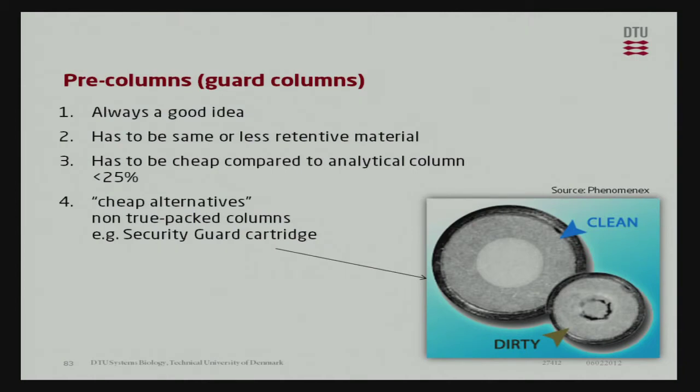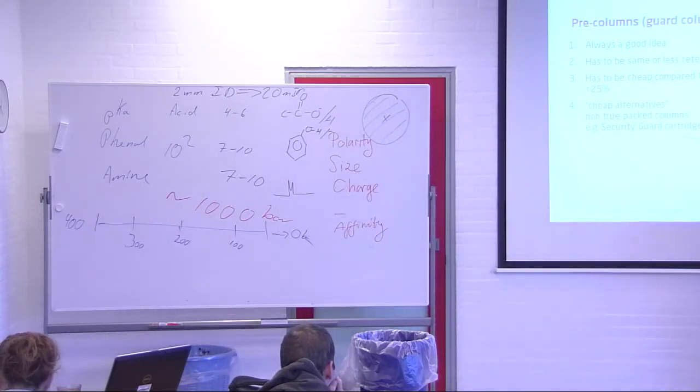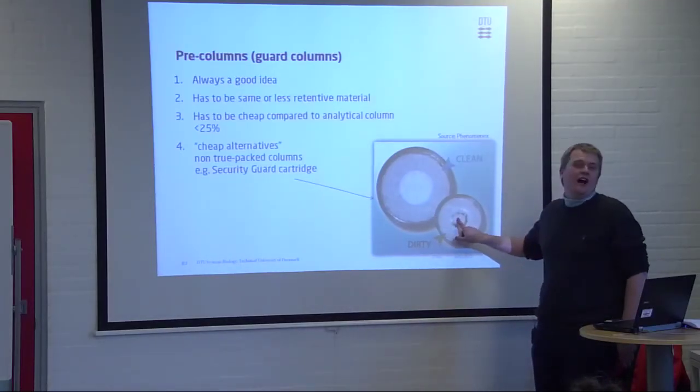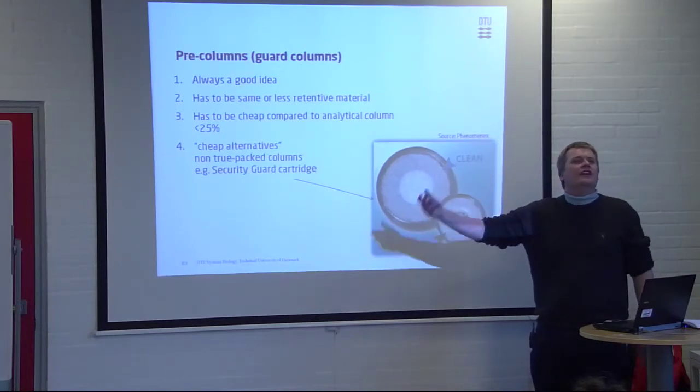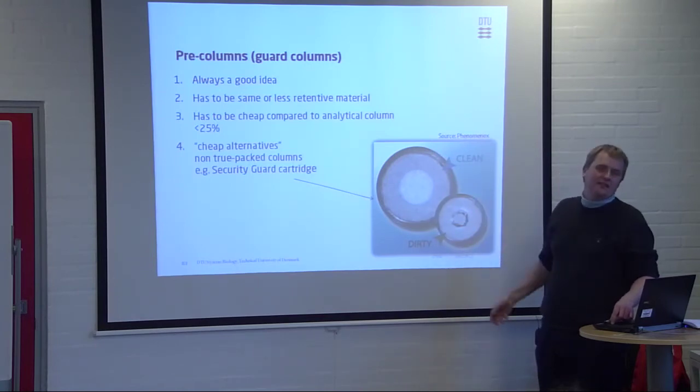And there's a lot of companies who call their stuff something like security guard or guard cartridge. These up here, a true guard column is actually packed exactly as your own column. They're usually too expensive. So, if we want a cheaper alternative, that's made in these guard columns. And again, dirty samples, we can change this every day. The important thing is, it's the same phase that is inside your column. So, the idea is that if it goes through the guard column, it probably also gets through the analytical column. And if it stopped there, well, it would probably kill the other one.